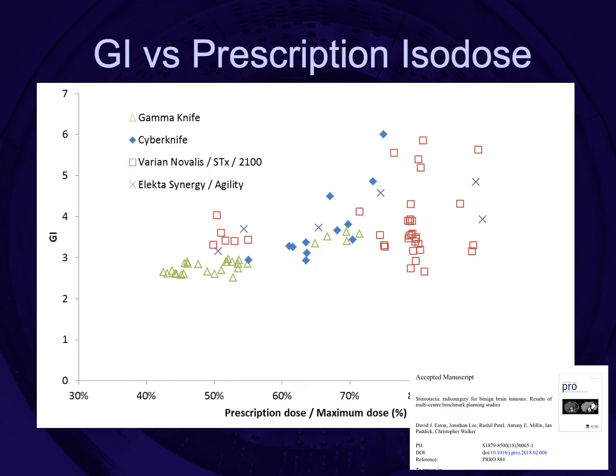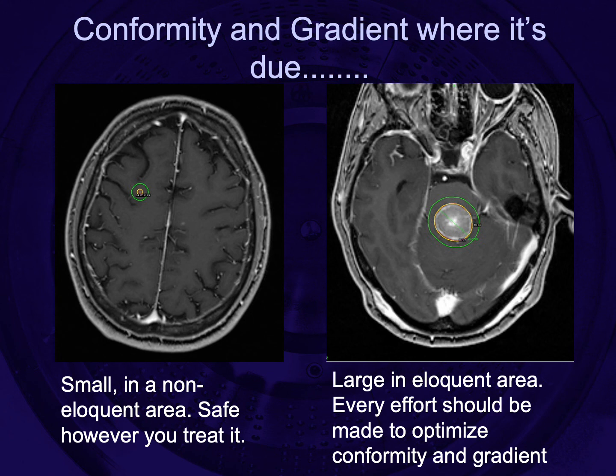This scatter plot shows results from NHS benchmarking tests looking at treatment parameters for different radiosurgery platforms. The lowest gradient indices come from Gamma Knife treatment plans, followed by CyberKnife, then stereotactic Linac. A general trend is visible: as you reduce your prescription dose and accept a higher maximum dose within your target, your gradient index tends to go down. So the lowest gradient indices tend to be associated with the lowest prescription isodoses.